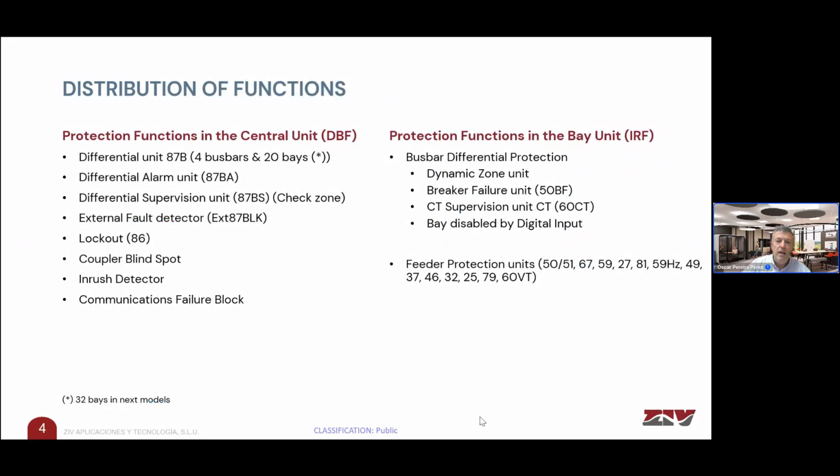In this distributed arrangement of our busbar differential protection, you should know that part of the protection functions are embedded into the central unit, the DBF, but there are also other specific protection functions that are included in each of the bay units, in each of the IRF.